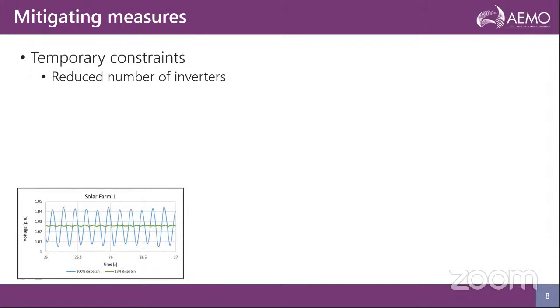The blue trace is the post disturbance voltage changes as seen in a simulation, which was also further verified by system test. When I say system test, it is a real-time test. So when you have all the inverters at 100% dispatch, you see this voltage oscillation popping up following a disturbance or a contingency. And when you reduce the number of inverters, the magnitude of this oscillation substantially reduces. So this was a temporary constraint which was put in place until we explore alternative solutions.